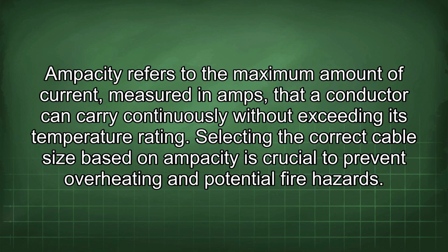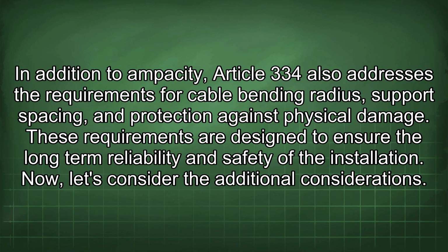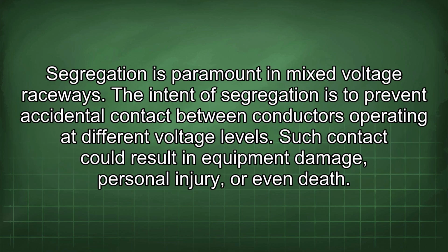Ampacity refers to the maximum amount of current, measured in amps, that a conductor can carry continuously without exceeding its temperature rating. Selecting the correct cable size based on ampacity is crucial to prevent overheating and potential fire hazard. In addition to ampacity, Article 334 also addresses the requirements for cable bending radius, support spacing, and protection against physical damage. These requirements are designed to ensure the long-term reliability and safety of the installation. Now, let's consider the additional considerations. Segregation is paramount in mixed voltage raceways. The intent of segregation is to prevent accidental contact between conductors operating at different voltage levels. Such contact could result in equipment damage, personal injury, or even death.